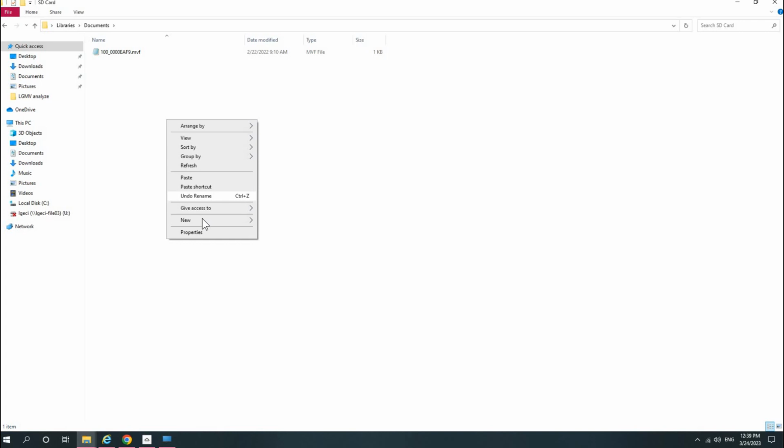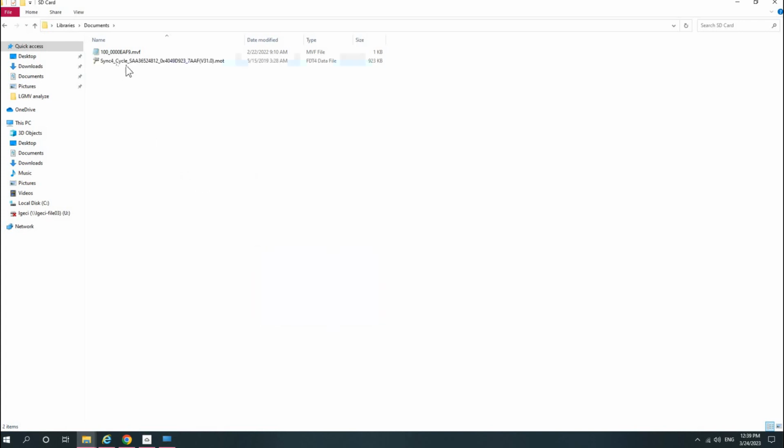I will paste the MOT software file. This software is for a Multi-V 4 heat recovery unit, main PCB. Now we need to make an MRF file, which will connect the software file with the stick writer brains. For this, let's make a copy of the template MVF file.